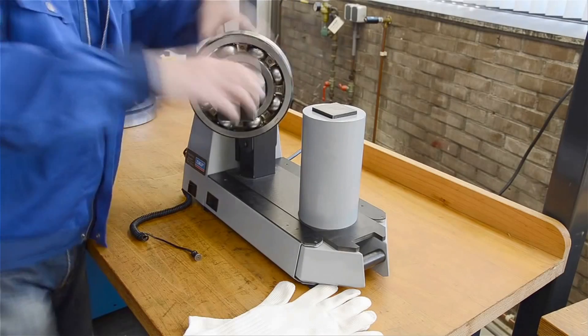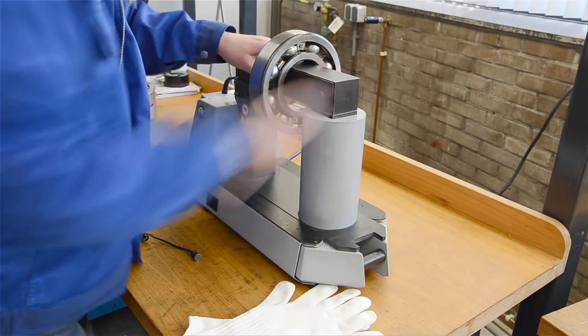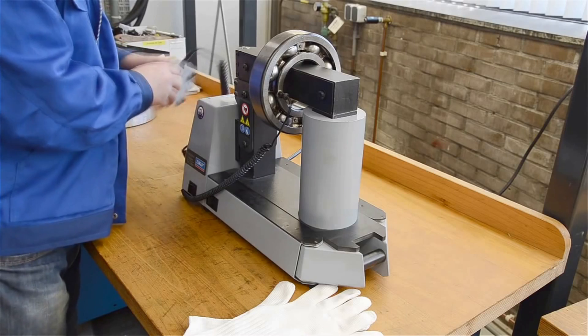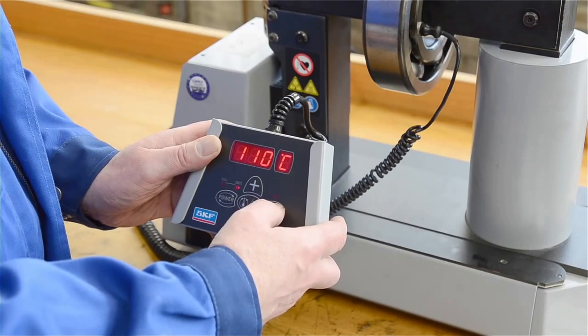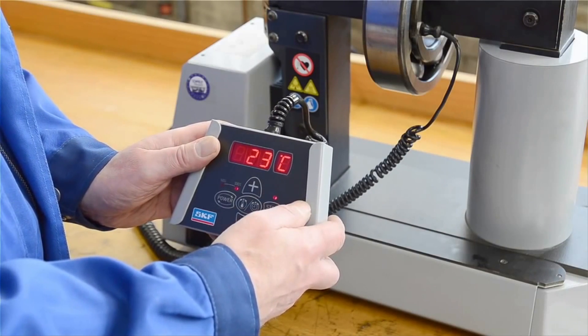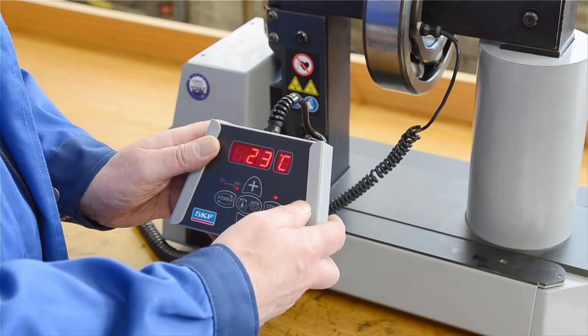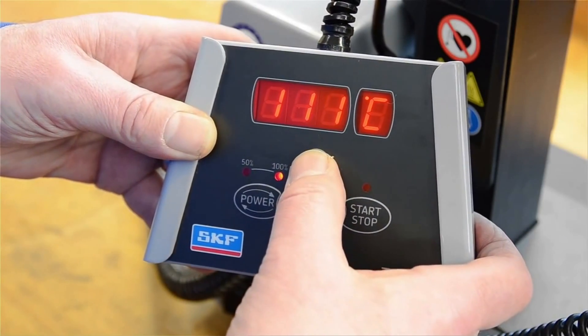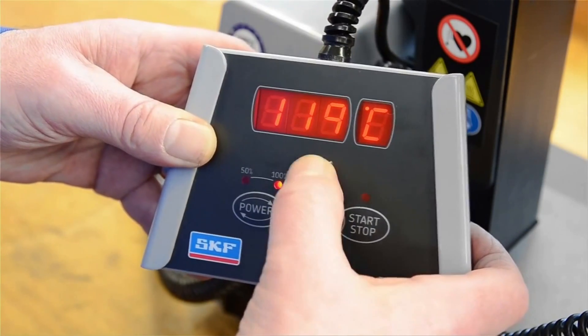Place the bearing on the heater and then place the temperature probe on the bearing inner ring. Press the start button on the remote control and the bearing starts heating. The preset temperature is 110 degrees Celsius, but you can also choose the temperature you want.